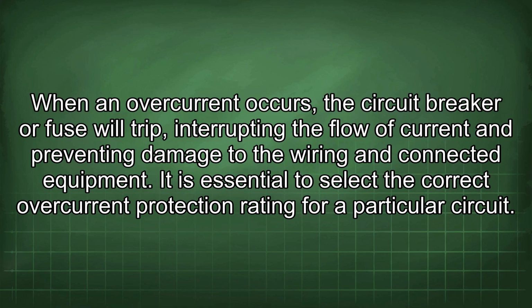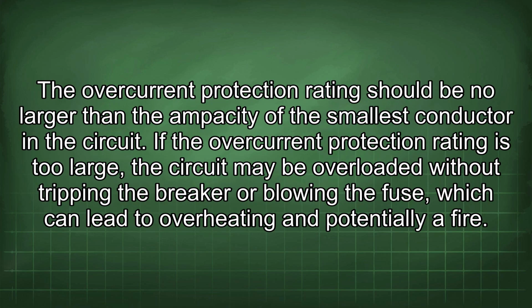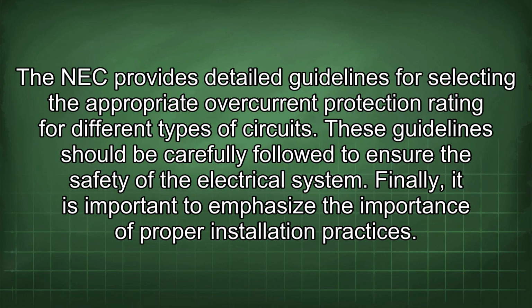It is essential to select the correct overcurrent protection rating for a particular circuit. The overcurrent protection rating should be no larger than the ampacity of the smallest conductor in the circuit. If the overcurrent protection rating is too large, the circuit may be overloaded without tripping the breaker or blowing the fuse, which can lead to overheating and potentially a fire. The NEC provides detailed guidelines for selecting the appropriate overcurrent protection rating for different types of circuits. These guidelines should be carefully followed to ensure the safety of the electrical system.